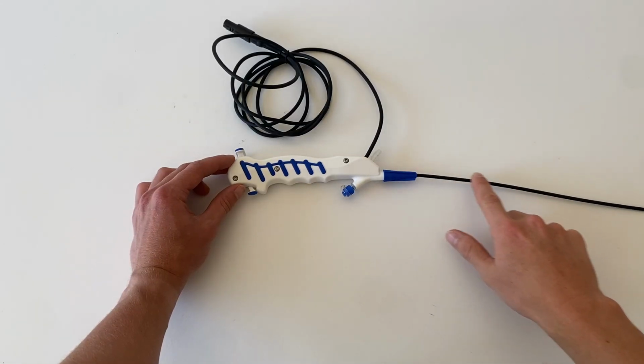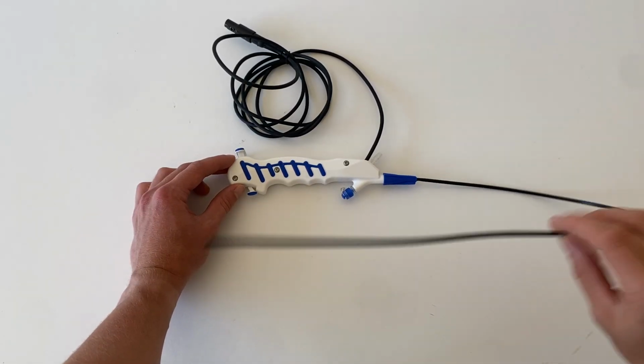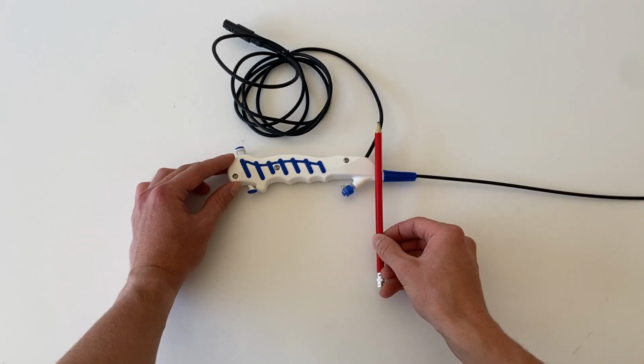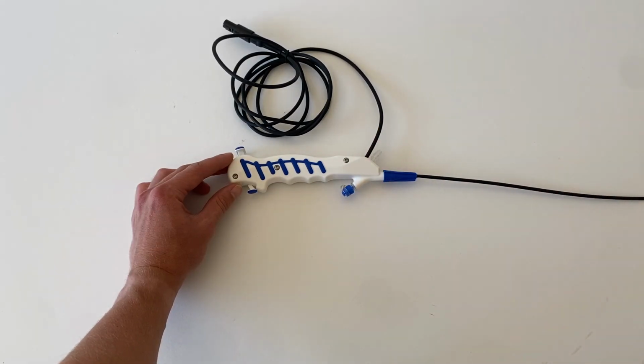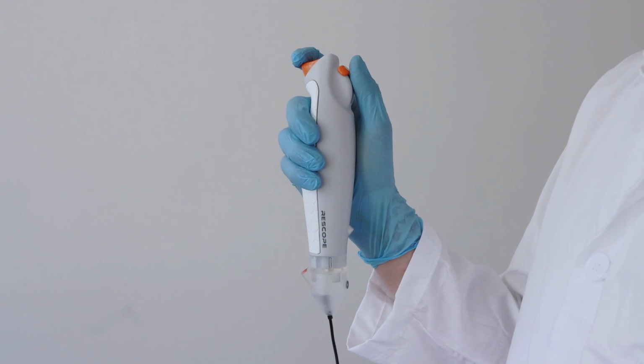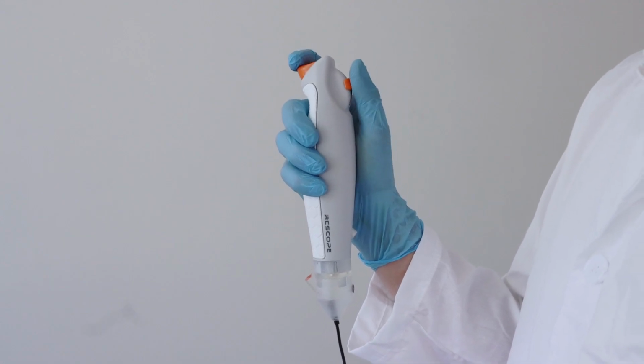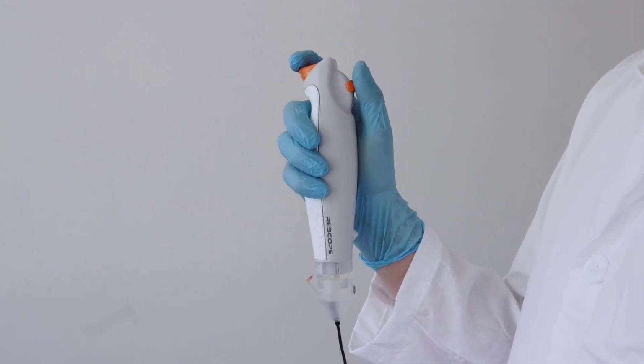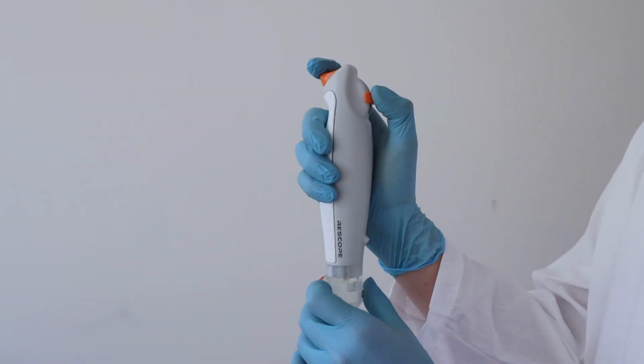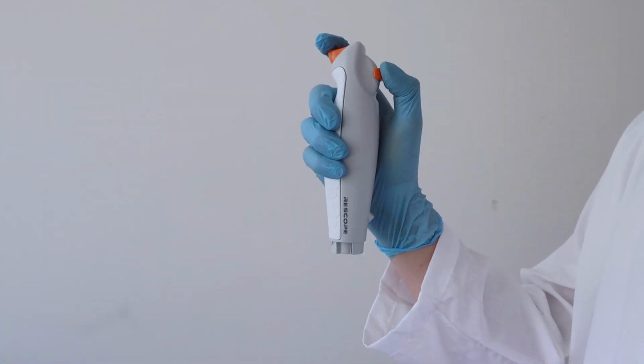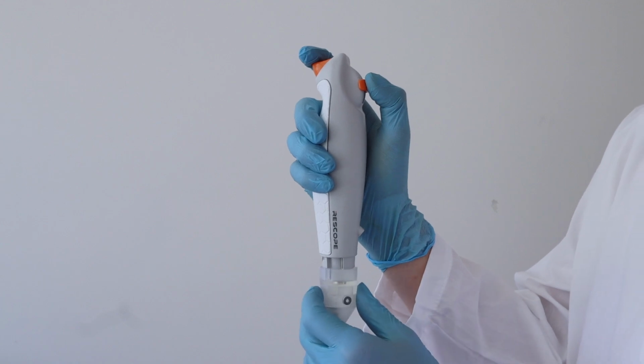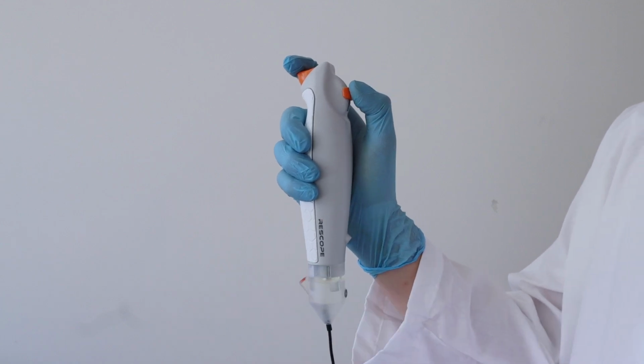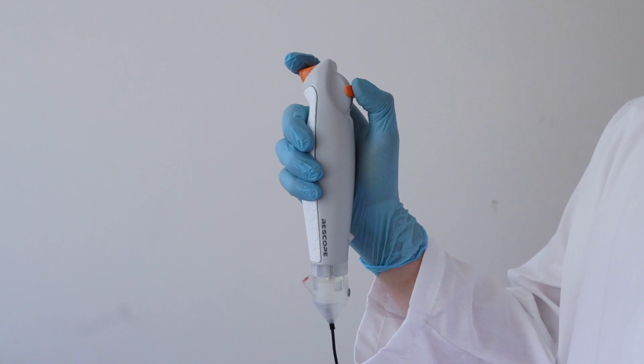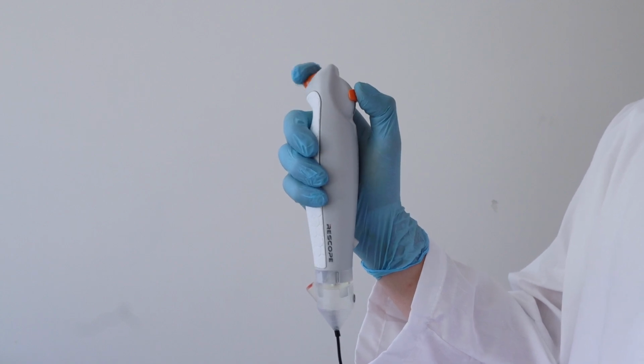And so the idea was to isolate that section where contamination occurs and make it replaceable, meaning the majority of the device is reusable. After each procedure, the contaminated insertion section can be easily removed and replaced with a brand new sterile one. And what this means is that 82% of the device, which includes all the expensive electronics and control mechanisms, is fully reusable, and only the part that goes inside the body is disposed.